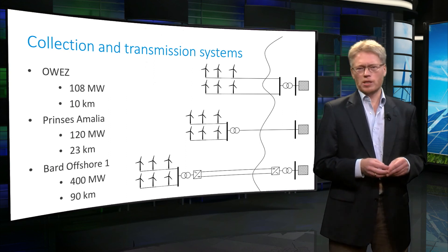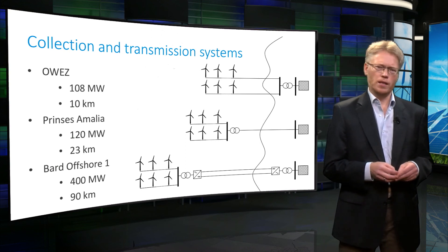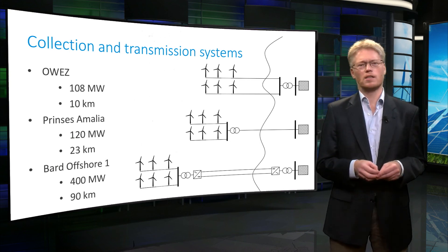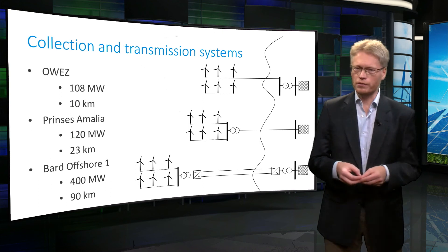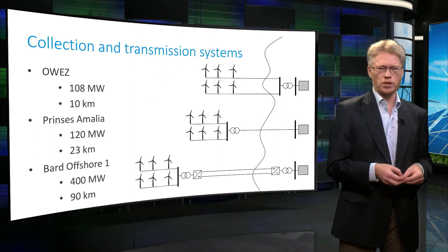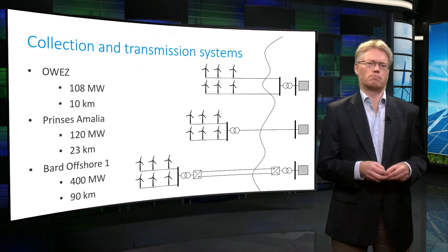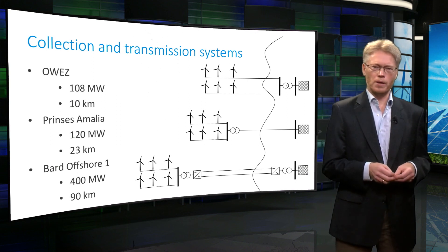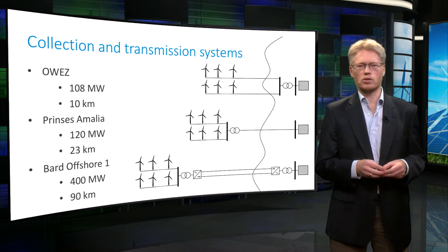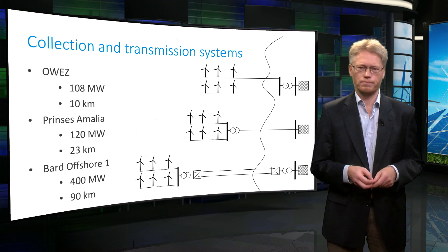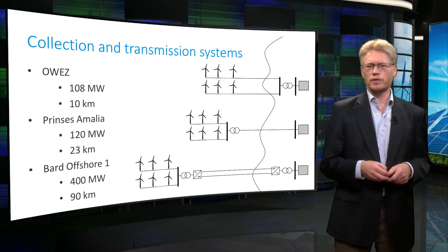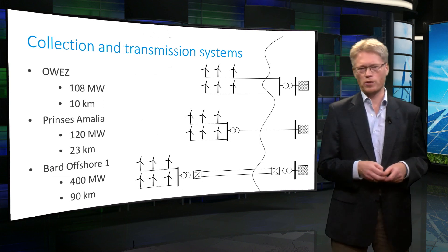The BARD offshore wind farm has a power level of 400 MW, and at 90 kilometers from shore it can be classified as far offshore. In this case, after the power collection, the voltage level is not only increased but also converted from AC to DC using power electronics. The reason to use direct current for the power transmission is that using AC at long distances is not feasible because of the large reactive power consumption of the cables. Because the offshore power system does not yet exist, a lot of research is done to investigate what the best offshore power system would look like.